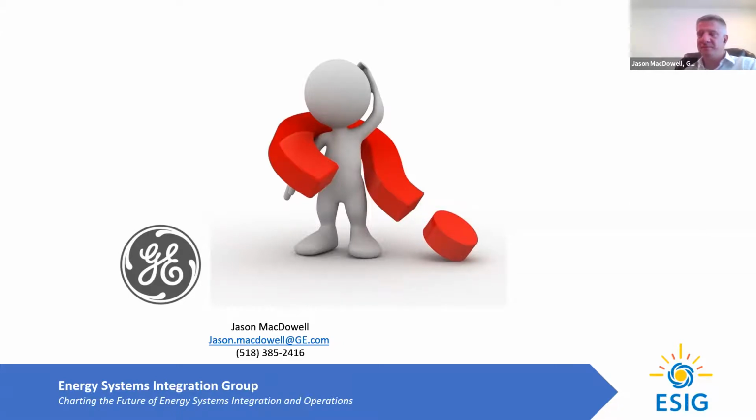Jason said this, but I want to say it again. We need to make the distinction between the requirement that the equipment have the capability to provide these services, voltage control and frequency response, and the actual use of those capabilities. Those are not synonymous. Yeah, exactly. FERC has ruled that it is mandatory to have the capability. Many systems, as is often the case, ERCOT's an example, use those capabilities very effectively.